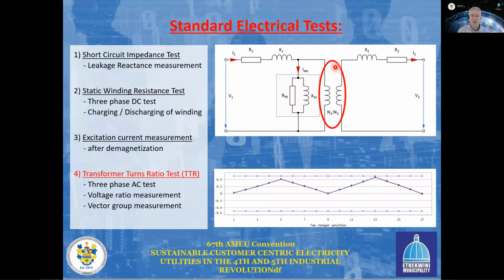Typical results will look like this. Again, we do this for all tap positions, and all 3 phases should obviously again be right on top of each other, because the transformer ratio should be the same for each phase. And also the measured transformation ratio should not deviate by more than 0.5% from the nameplate data that is on this transformer.